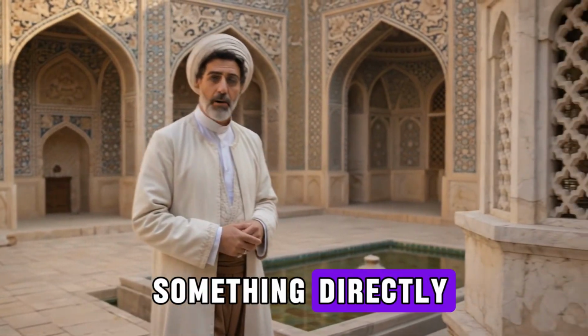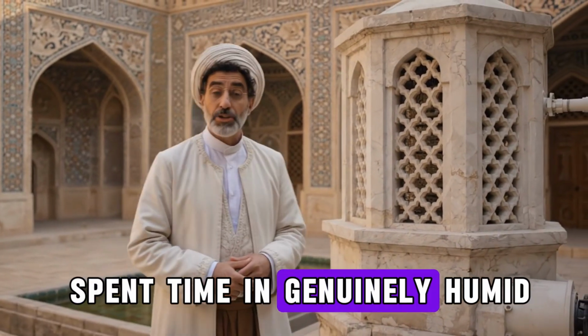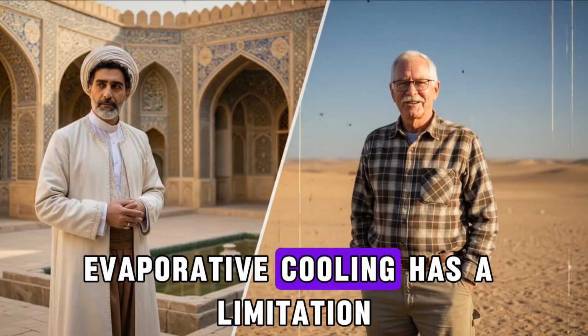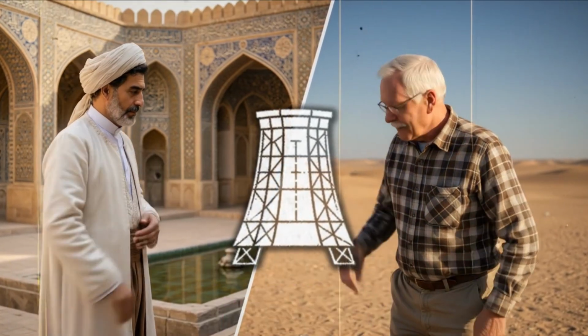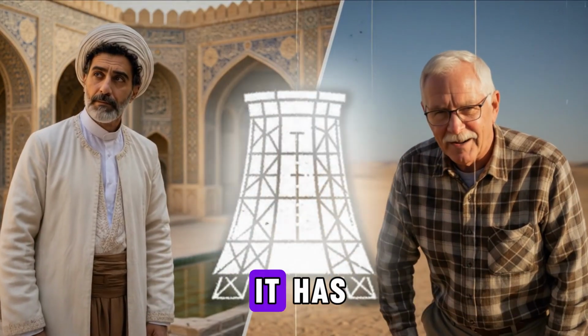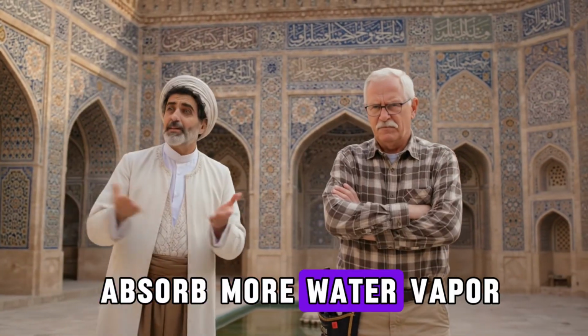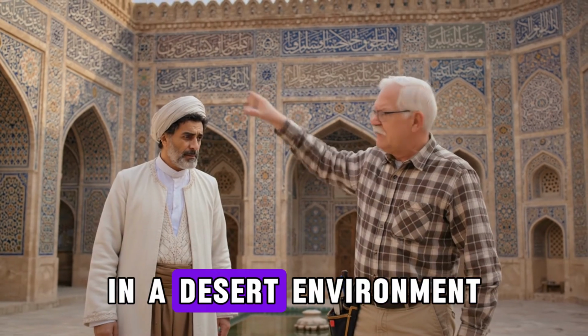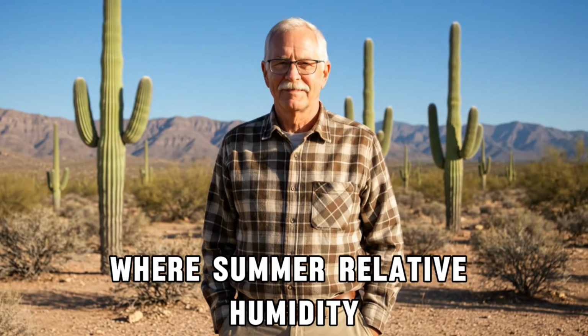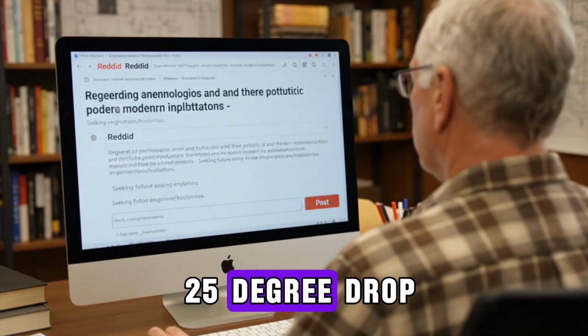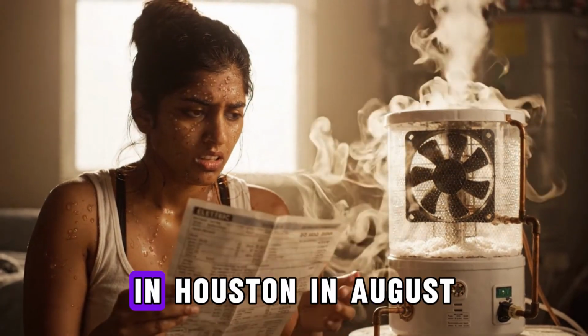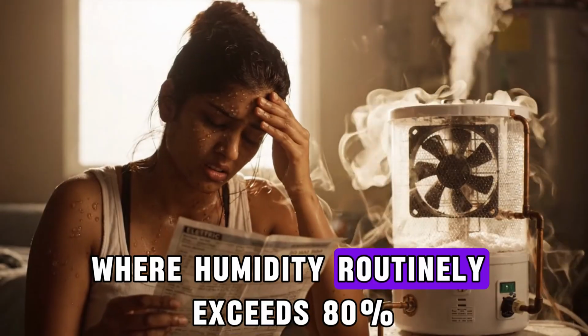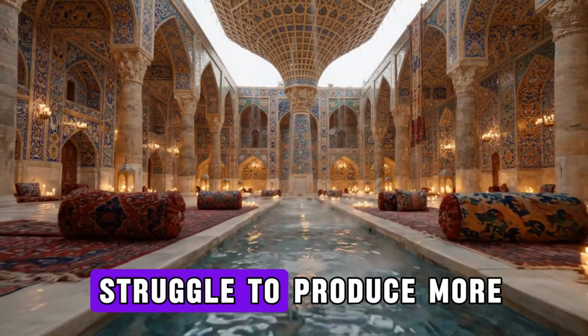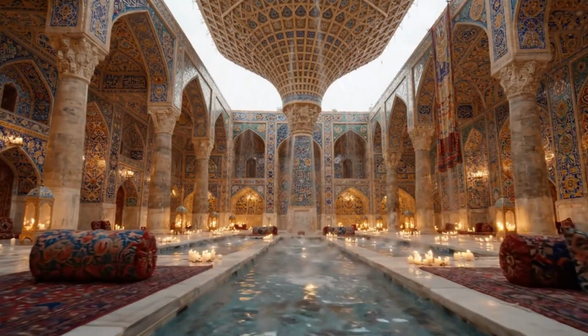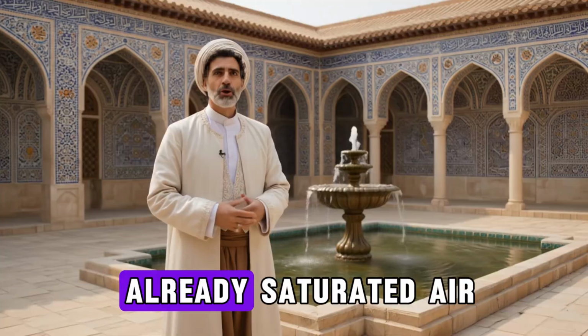Now I want to address something directly, because anyone who has spent time in genuinely humid climates is already thinking it. Evaporative cooling has a limitation, and that limitation is humidity. The drier the air, the more cooling potential it has, because dry air can absorb more water vapor before reaching saturation. In a desert environment like Phoenix or Tucson, where summer relative humidity often drops below 15%, an evaporative cooler can produce that full 25-degree drop with almost no loss in efficiency. In Houston, in August, where humidity routinely exceeds 80%, the same device will struggle to produce more than a 5 or 6-degree drop, and it may actually make the room feel worse by adding moisture to already saturated air.